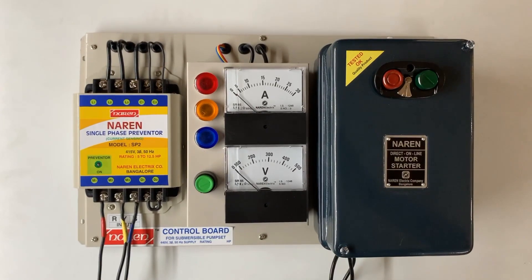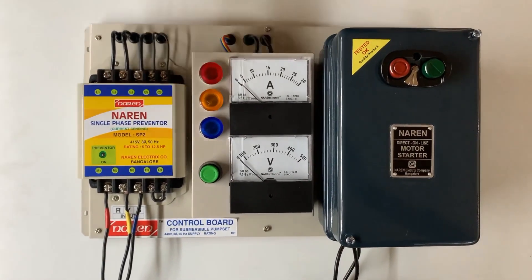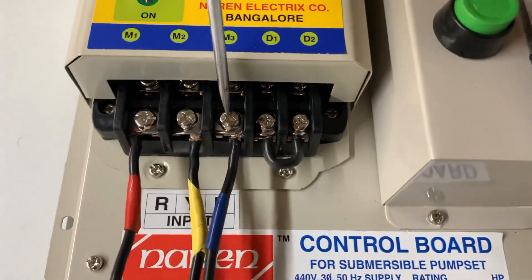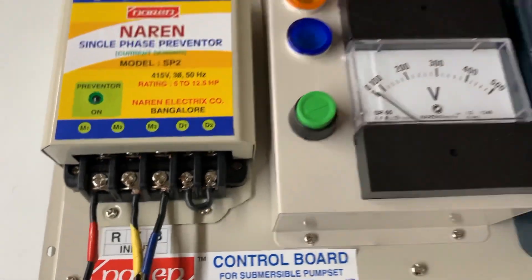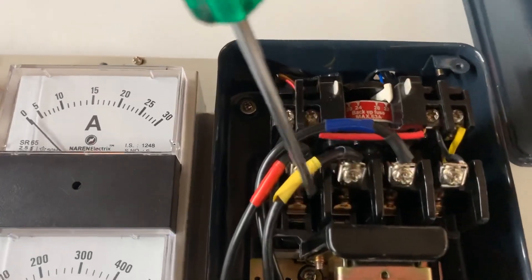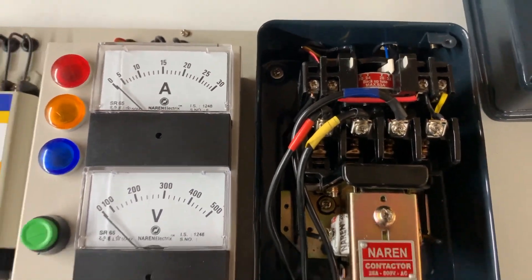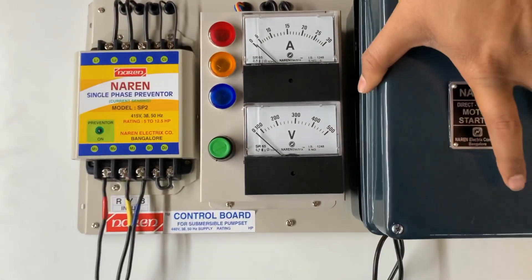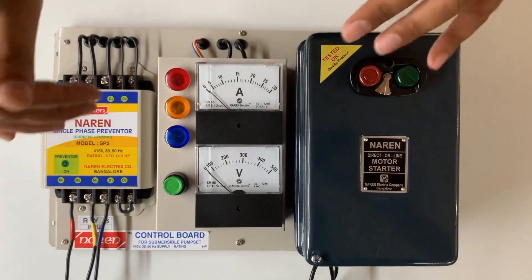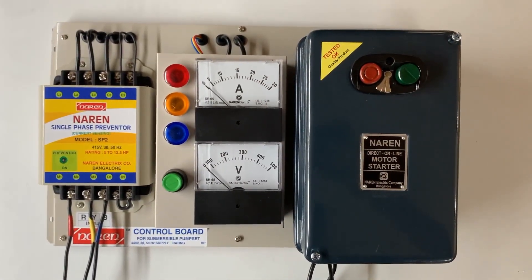The whole assembly comes in the control board, completely wired, and it's easy and economical to install. The incoming three-phase supply is to be connected to these three terminals — R, Y, and B. The motor cables are to be connected to the starter at these points. All other wiring is done by the company, so the whole assembly comes with all wiring done.